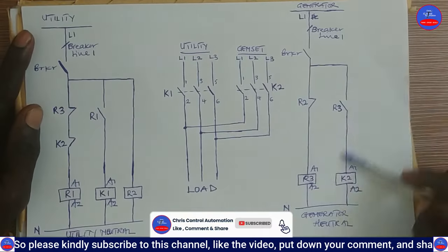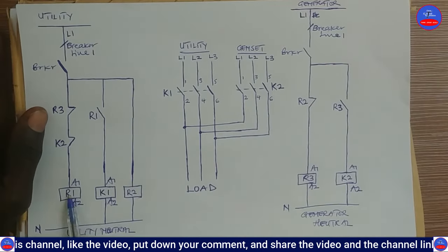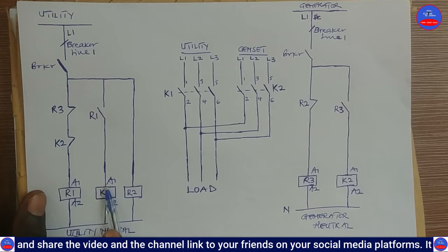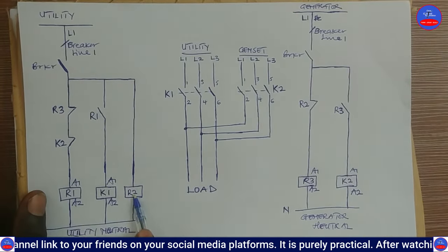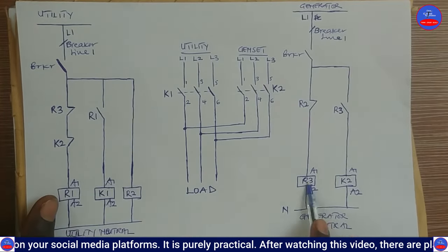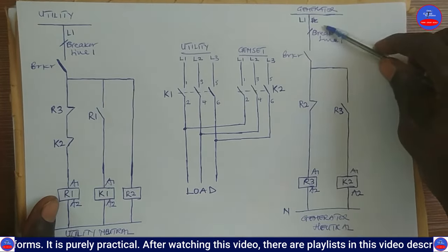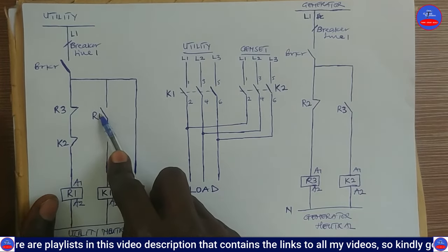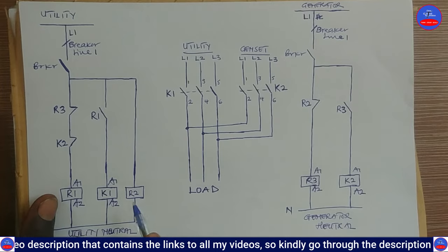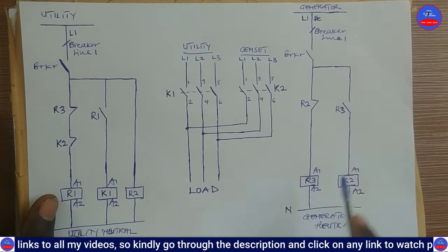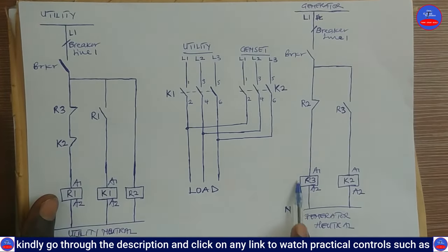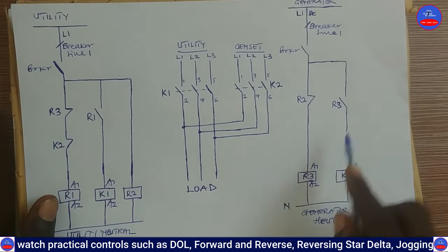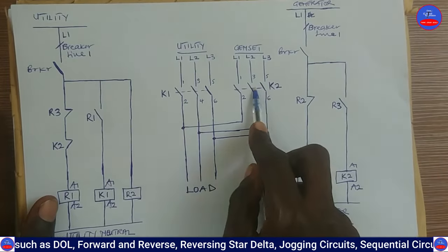This is the control circuit for the utility side and this is the control circuit for the generator side — they are all off right now. These are the relays and contactors. This is the main relay R1 for the utility line, this is the main contactor K1 for the utility side, and R2 is another relay for the same utility side. R3 and K2 are for the generator side. R1's open contact is here, R2's close contact is here, R3's close contact is here, and K2's close contact and R3's open contact are also identified.